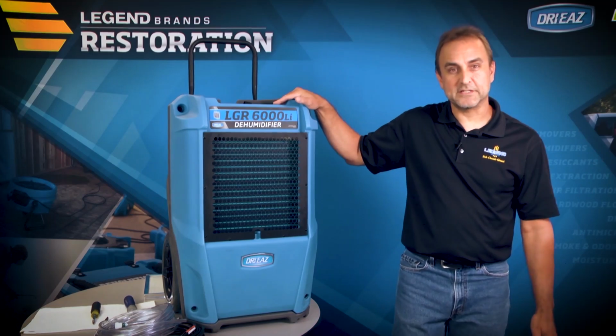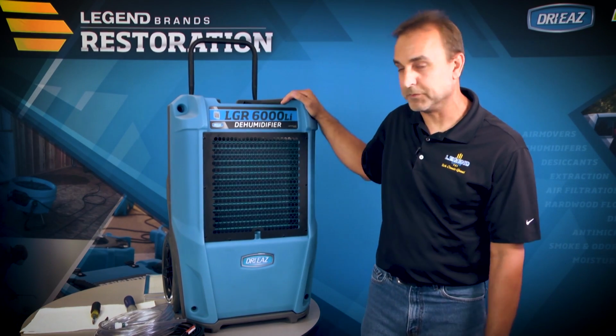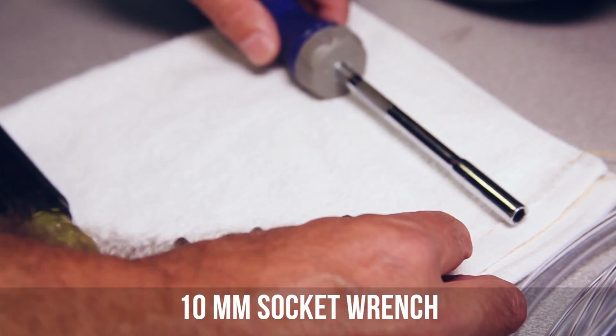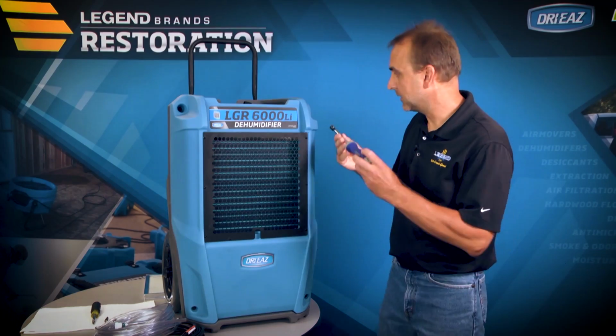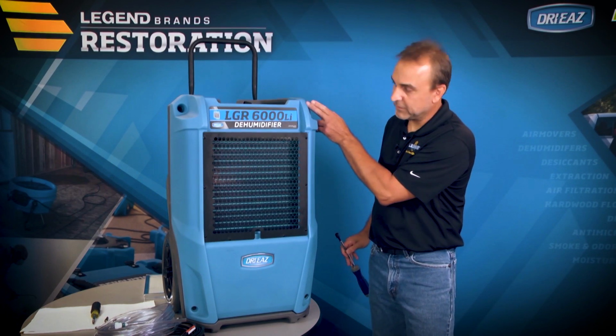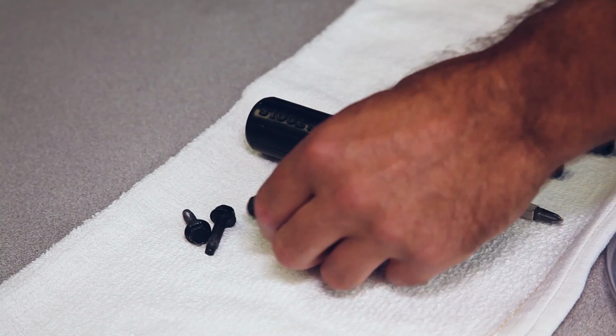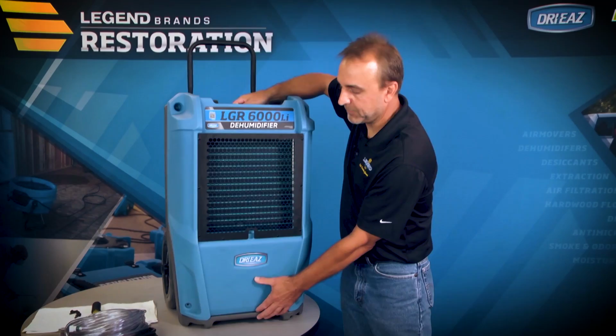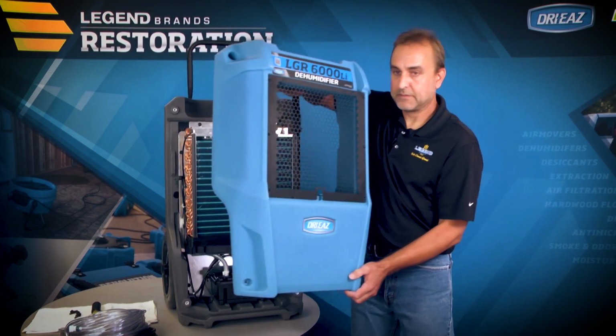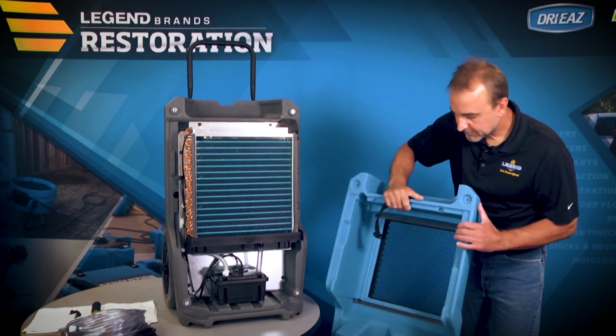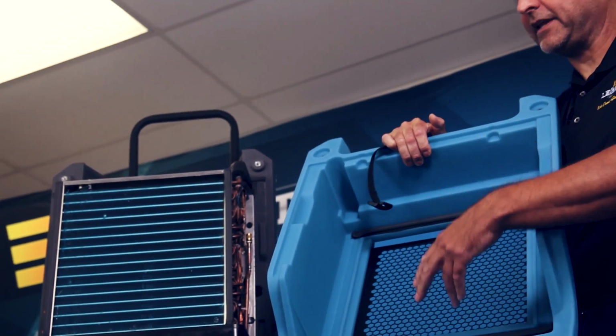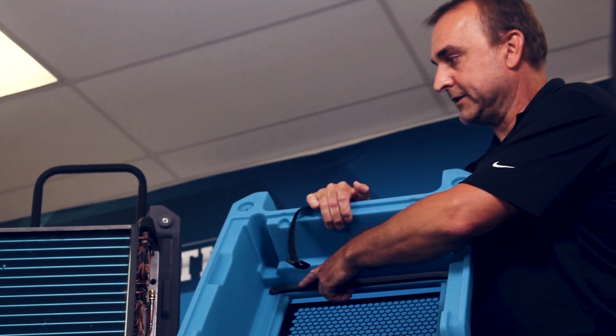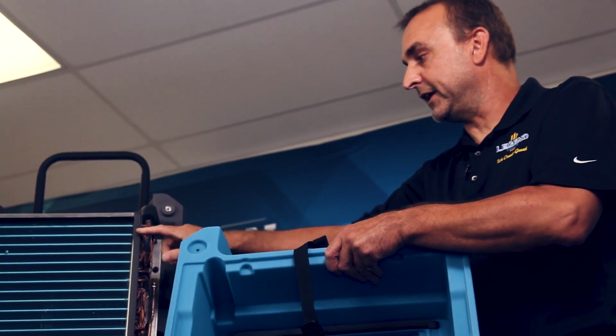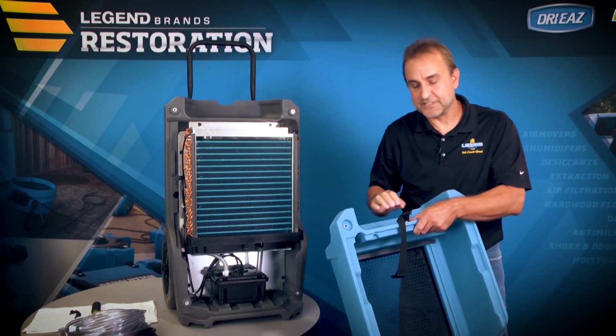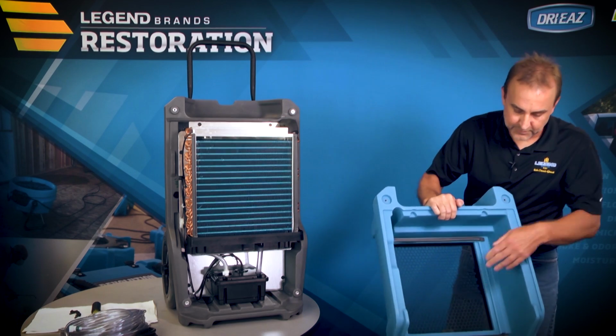The LGR 6000 Li is the simplest unit on the market to maintain with a 10 millimeter socket. There are 4 bolts you want to remove, 1 on each corner of the top and 1 at each corner on the bottom. Remove the front cover by lifting from the top. And do notice the gasketing on the inside of the front cover, the top and the bottom, and the gasketing at the sides of the coils. If the gasket is damaged or deteriorated, you'll need to replace.